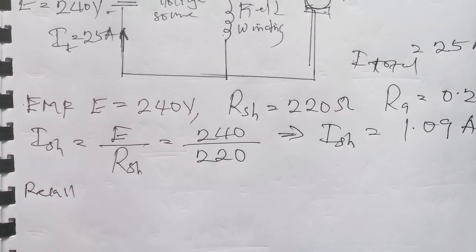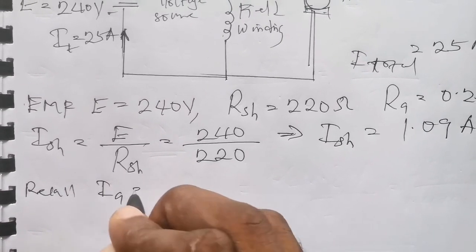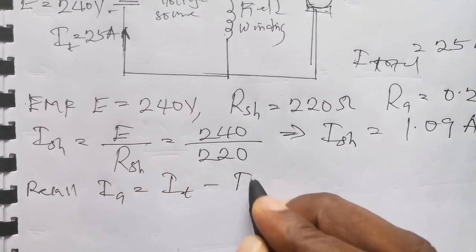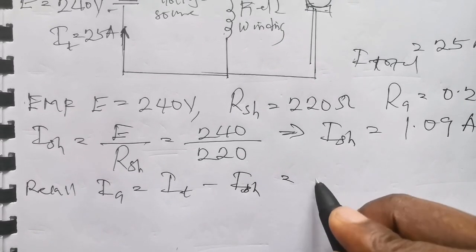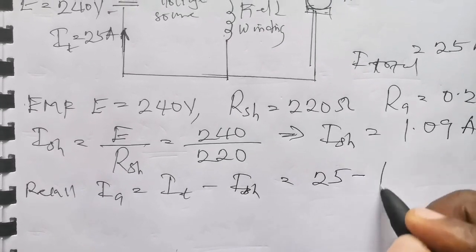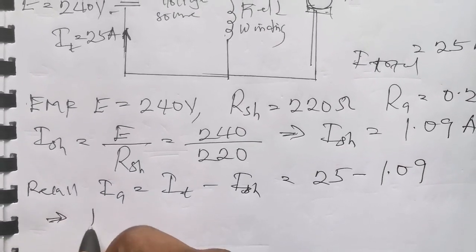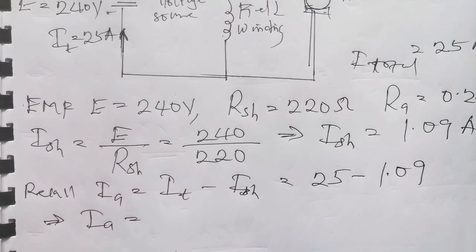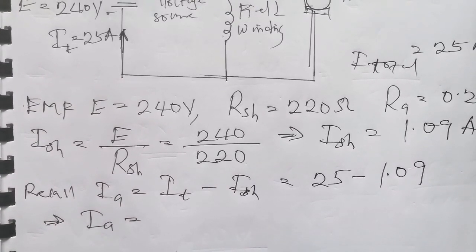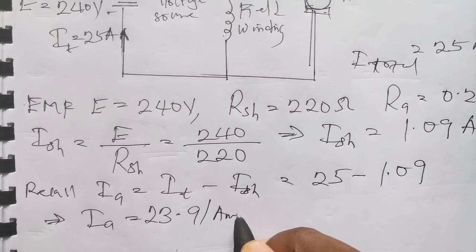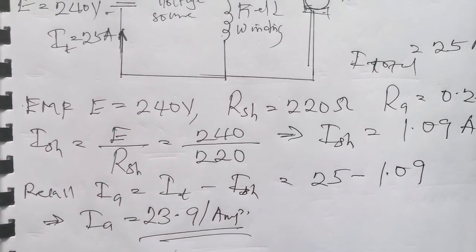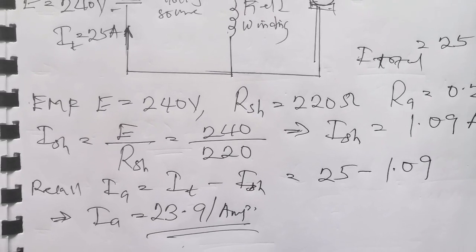Recall that the armature current is given as total current minus the shunt current. So Ia = 25 amps minus 1.09, which gives us 23.91 amps. So our armature current is 23.91 amps.